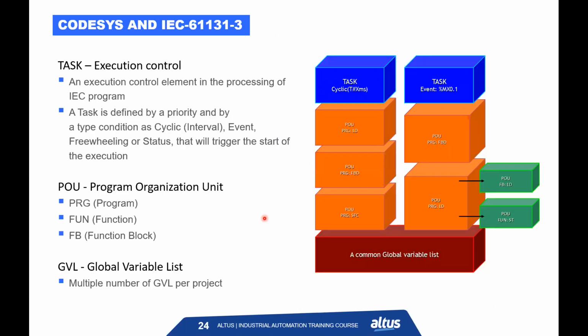Let's talk a little bit about how CODESYS works. We have a task, an execution control element in the process of the IEC program. A task is defined by a priority, so we can have more than one task with different priorities. We can choose to run the task cyclic, event-driven, freewheeling, or by status, which will trigger the start of the execution.